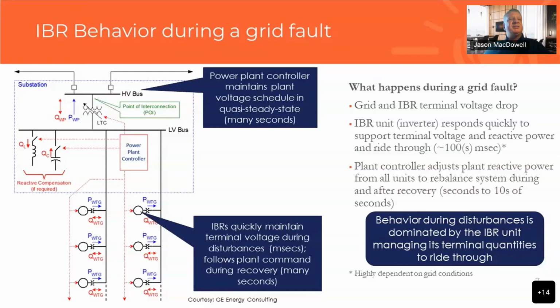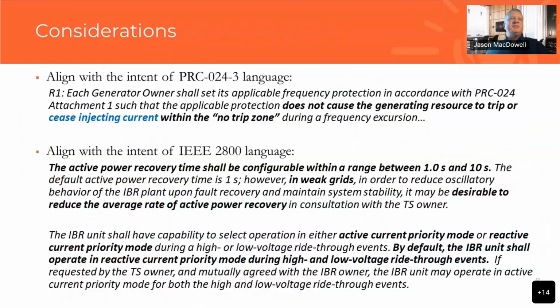But during disturbances, the behavior in the very short amount of time during and just after the disturbance is dominated by the inverter-based resource control. So one thing that could be good to consider is that during the disturbance, instead of only calling out what the plant voltage is doing, we make sure the inverter-based resource adequately manages its own reactive current and its own terminal quantities in order to ride through. And then when the fault clears, we can make sure to recover the voltage as needed through coordinated hierarchical control at the plant level. So, just some considerations and options for harmonization of the language before we break here and go to the next session.